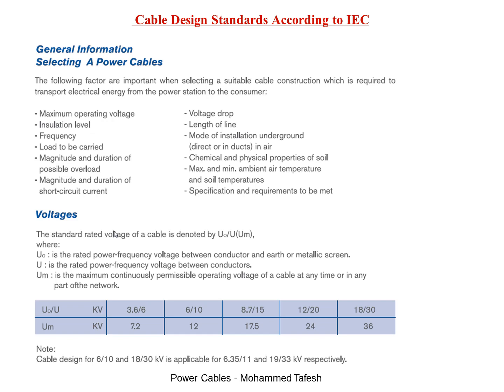The first condition which is very important in the design of a power cable, related to IEC, is the voltages. The standard rated voltage of a cable is denoted by U0/U or UM, where U0 is the rated power frequency voltage between conductor and earth or metallic screen, U is the rated power frequency voltage between conductors, and UM is the maximum continuously permissible operating voltage of a cable at any time or in any part of the network.